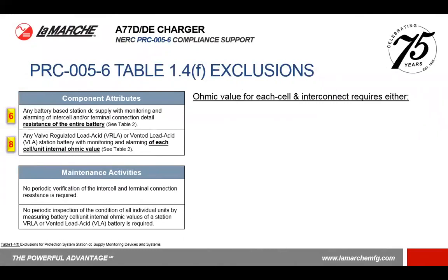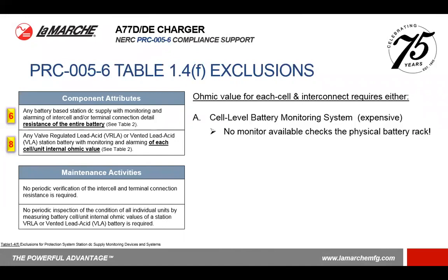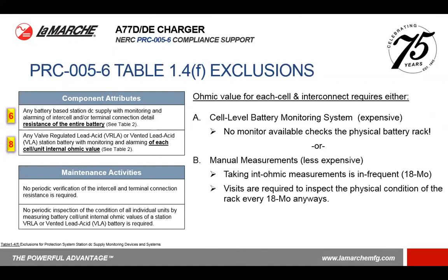Points 6 and 8 we've grouped together because they both refer to measuring the intercell and/or terminal connection resistance of the battery, as well as the cell unit internal ohmic measurements. So the ohmic value of each cell and interconnect requires a cell-level battery monitoring system, which can be expensive and very extensive. Normally on a system like this, you'll see voltage probes on each cell of the battery, as well as possibly across the interconnection straps of the battery, in order to make measurements in situ.